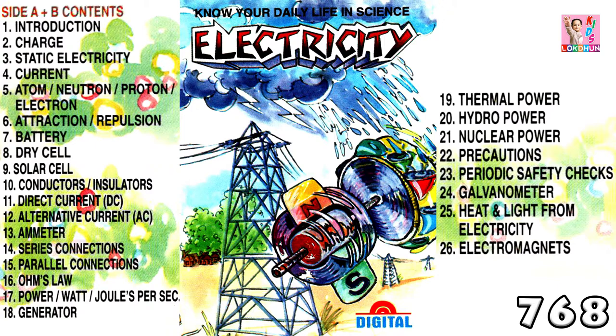You know that the main supply is 220 volts. As 1 ampere equals 1 watt divided by 1 volt, the current used by the hot plate plus the bulb plus the iron equals 1850 divided by 220, which is 8.4 amperes. Just imagine, the hot plate, the bulb and the iron will forcefully draw their required 8.4 amperes of current from your plug point, which can safely supply only 5 amperes.